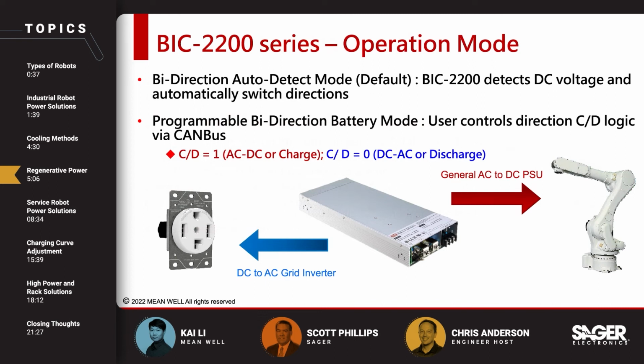So for the automatic detection mode, the BIC-2200 will detect the DC voltage. If the voltage on the output side is higher than its output voltage set point, it will go into the DC to AC inversion mode. But if there's no voltage on the output side or low voltage on the DC side, it would just be the normal AC to DC power supply. So in the scenario of powering a robotic arm, during the normal operation, of course, it will take power from AC and drive the motor.